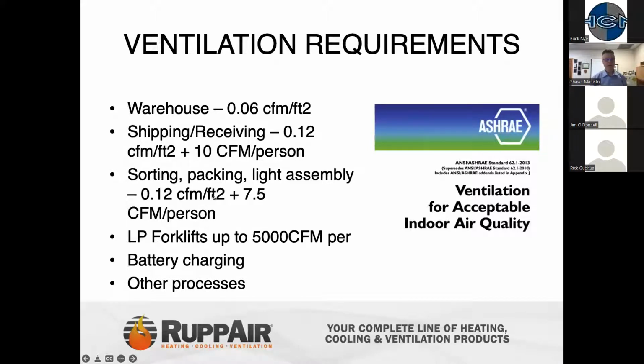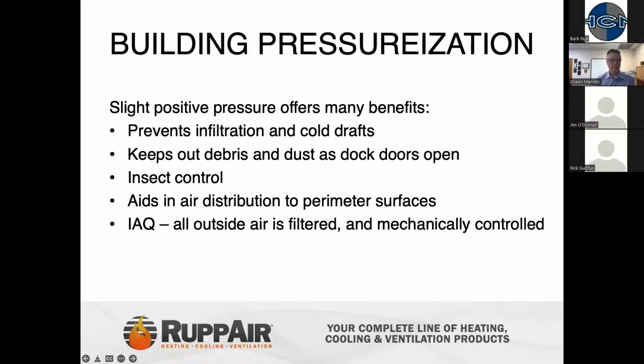On top of that, if you have occupied facilities running LP forklifts, that can be a big impact on the emissions or the indoor air quality of that facility, and those require up to about 5,000 CFM per forklift. Other things that we need to take into account are the battery charging areas and other processes that might be in place. However, it may be a warehouse, they may have some light assembly or some welding going on in this type of warehouse.